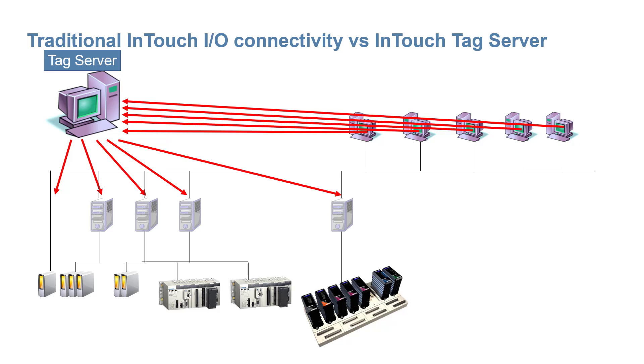Whereas the demand on the back-end data sources is the difference between crashing this old infrastructure and a working system. The tag server makes a request for fresh data from the plant equipment and caches the response. Then the tag server handles multiple requests for the same values for many clients.